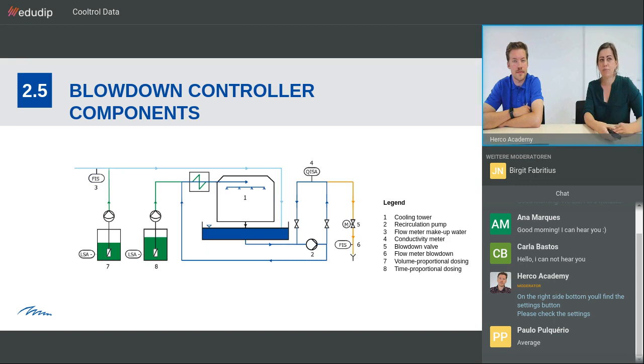So the final components of the system really are the dosing systems, here number 7 and 8. Usually there is one volume proportional dosing. This is the corrosion inhibitor. This dosing is done proportional to the makeup water that is coming in. So it's controlled by the makeup water flow meter signal. And number 8 is the time proportional dosing or time controlled dosing.